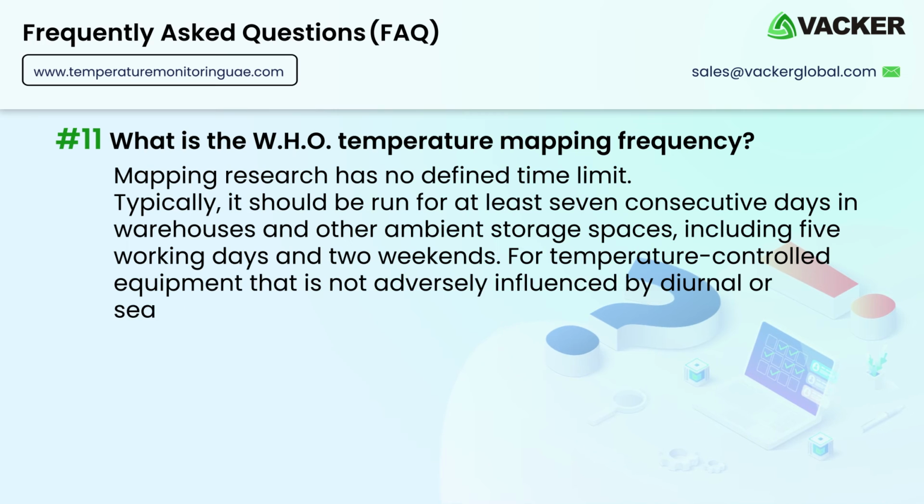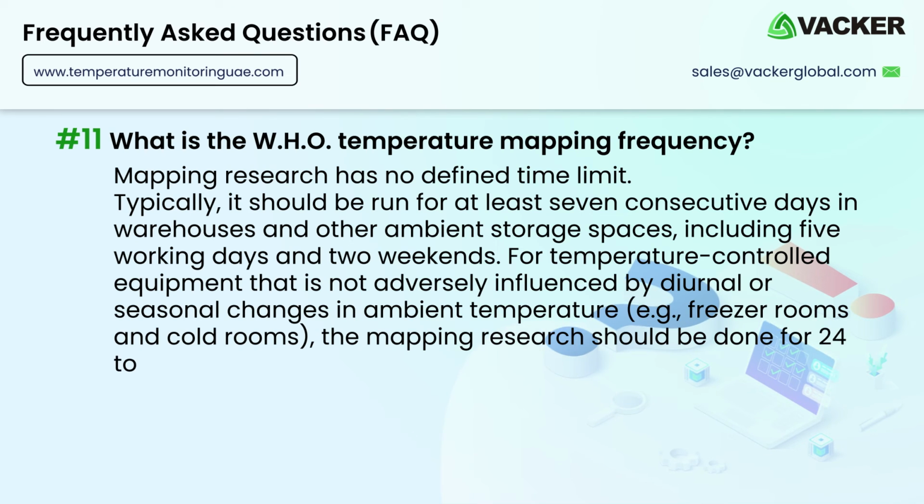Typically, it should be run for at least 7 consecutive days in warehouses and other ambient storage spaces, including 5 working days and 2 weekends. For temperature-controlled equipment that is not adversely influenced by diurnal or seasonal changes in ambient temperature, for example, freezer rooms and cold rooms, the mapping research should be done for 24 to 72 hours, or longer if necessary.